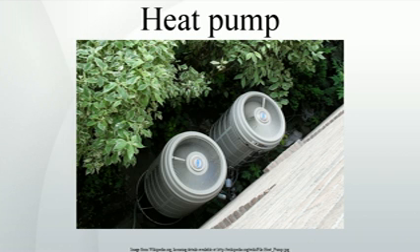An absorption heat pump may be fueled by natural gas or LP gas, for example. While the gas utilization efficiency in such a device, which is the ratio of the energy supplied to the energy consumed, may average only 1.5, that is better than a natural gas or LP gas furnace, which can only approach 1.